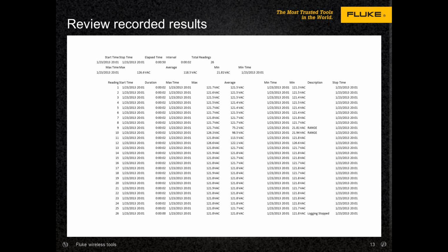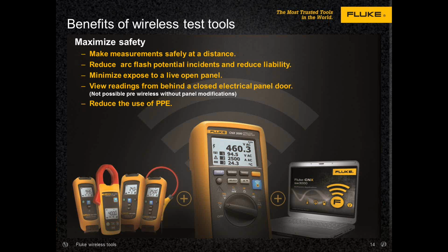So there's no issues there. I want to touch a bit on when you'd want to use multiple PC adapters. The only time that really comes into play is if you're in a facility commissioning brand new power or something like that, and you have multiple three-phase panels you want to look at, needing more than three, four, or five readings per panel across multiple panels.